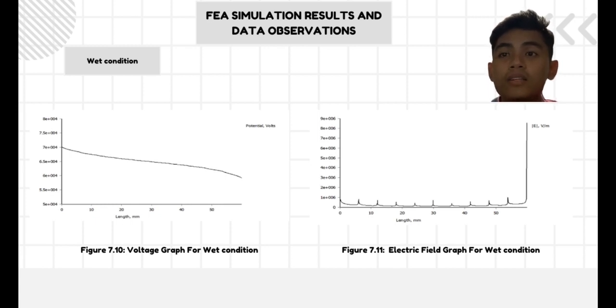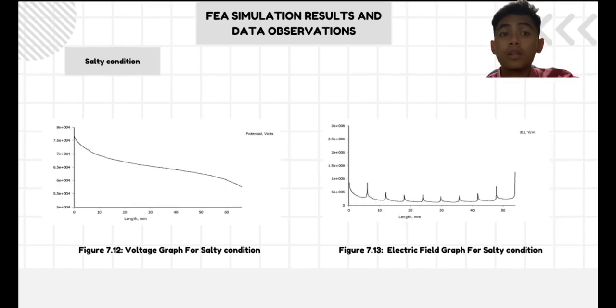This can result in an uneven charge distribution, increasing the electric field and causing potential issues such as partial discharge or flashover. It can also facilitate the dissipation of electric charge from the surface of the insulator. For the last result, that is the salty condition.